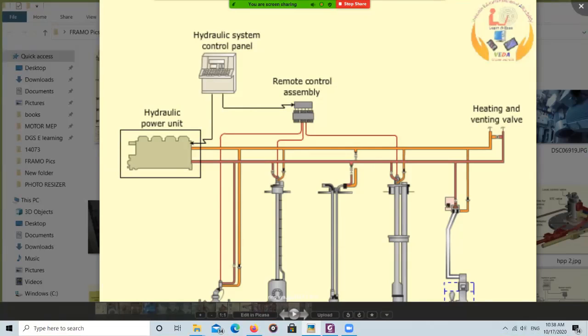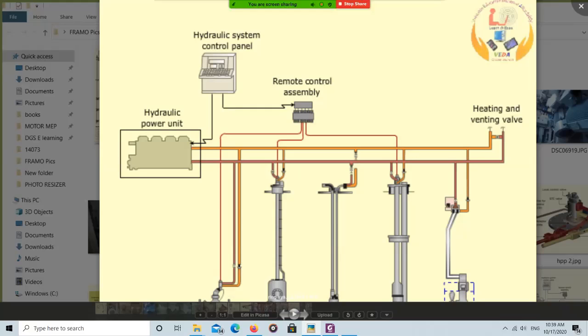Generally in a positive displacement pump, the discharge is fixed. In this variable displacement pump, the discharge is variable and you can control it by controlling the swash plate angle — adjusting as per requirement, whether you are using more or fewer pumps, or running at more or less RPM. The main purpose of this pump is to provide the hydraulic power required to drive all the cargo and ballast pumps.